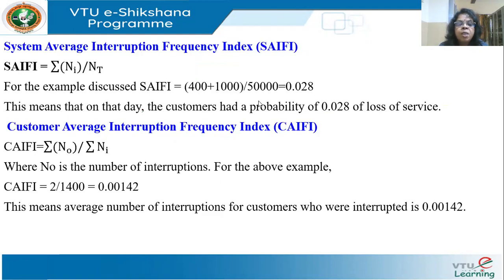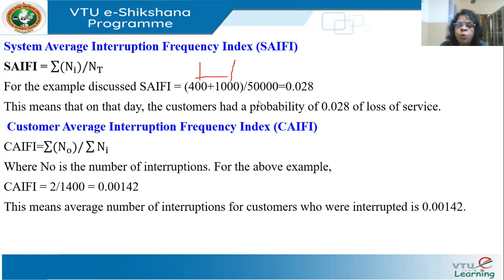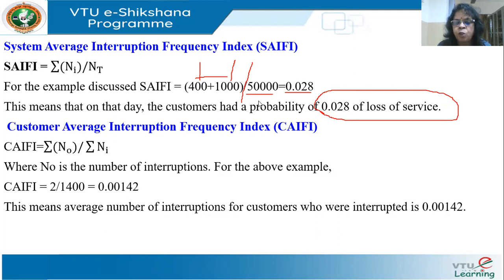Then we have SAIFI — System Average Interruption Frequency Index — which measures how frequently a customer is affected. It is given by sigma NI divided by NT. The first interruption affected 400, the second affected 1,000, so the sum of the two as a ratio of the total 50,000 is 0.028. This means on one day the customers had a probability of 0.028 of loss of service — a 2.8% probability that a customer will have an interruption.